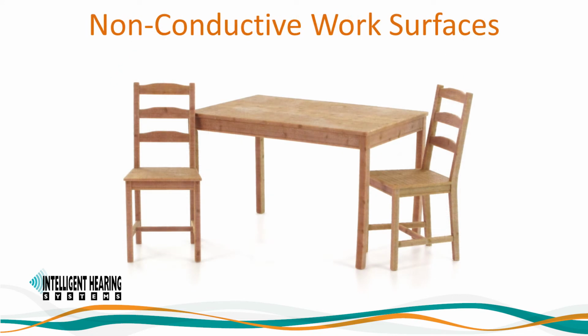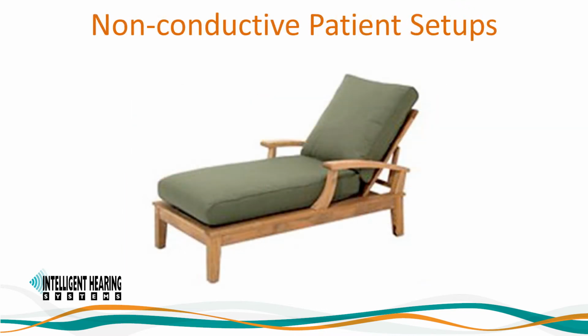Equipment needs to be set up in a methodical fashion. IHS recommends a wooden or plastic non-conductive work surface when placing the system components. Each system component must be isolated from any metal surfaces. The same is true for the patient's setup location. Patients should be set up on wooden or plastic non-metal and non-conductive chairs and beds that recline and are comfortable for testing. For ABR and ASSR testing, it is best that patients sleep comfortably.